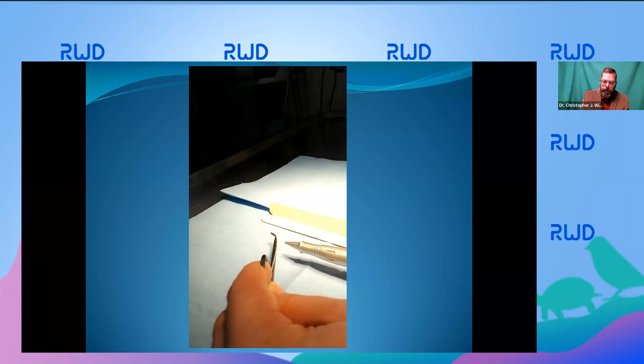One of the most frequent safety issues one can encounter with the use of the CO2 lasers is the reflection of laser light, especially off of metallic surgical instruments. If the tissue you're cutting or ablating is being held by a metal instrument, such as an ovarian pedicle within a clamp, aim your laser at the tissue without hitting the instrument. Reflecting off the instrument can occur randomly around the OR, making eye safety paramount. It can rebound right back at you, hitting your fingers, and at the very least, probably requiring you to re-glove. It can ignite surrounding drape material and damage the patient. You can use a moist backstop to help prevent this. And don't hit your technicians.